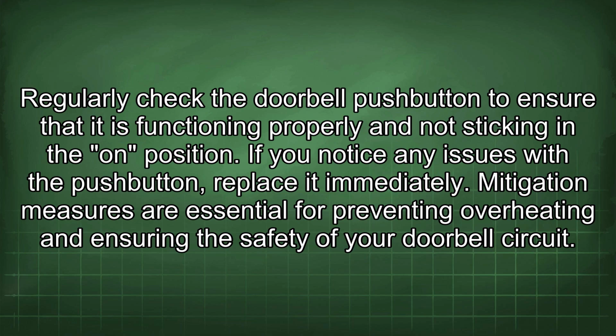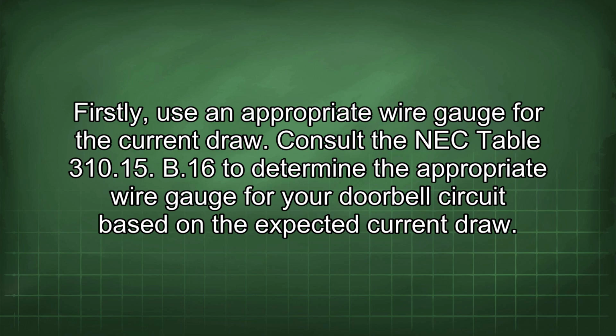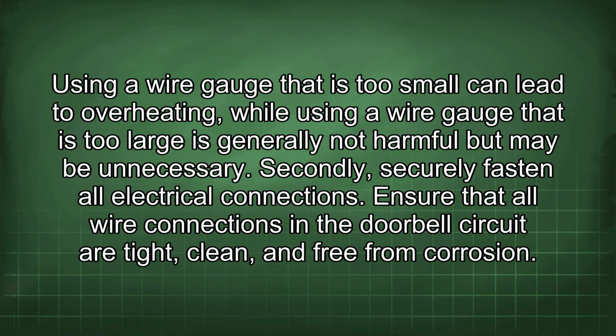Mitigation measures are essential for preventing overheating and ensuring the safety of your doorbell circuit. Firstly, use an appropriate wire gauge for the current draw. Consult the NEC Table 310.15(B)(16) to determine the appropriate wire gauge for your doorbell circuit based on the expected current draw. Using a wire gauge that is too small can lead to overheating, while using a wire gauge that is too large is generally not harmful, but may be unnecessary.